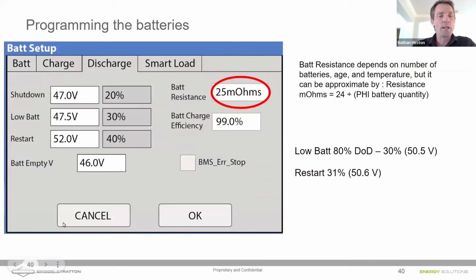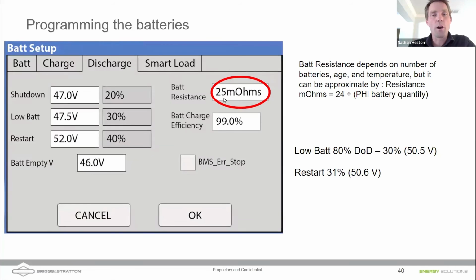It's also worth pointing out that there is a resistance calculation that you do to put into the Sol-Ark 15K. And I'm highlighting what that is. So you might have your low battery cutout set at, let's say, 48 volts. But you might notice that when you're powering a lot of loads, the inverter will keep drawing from your battery, even though you're below 48 volts. You might be at 47 or 46.